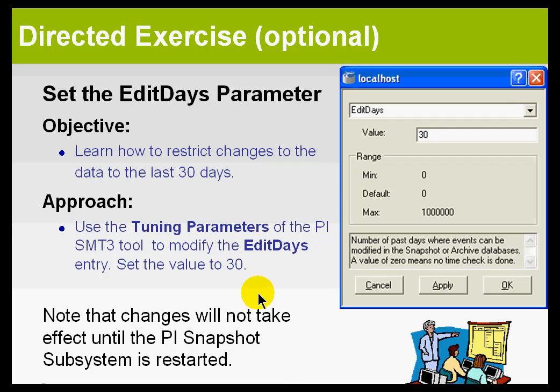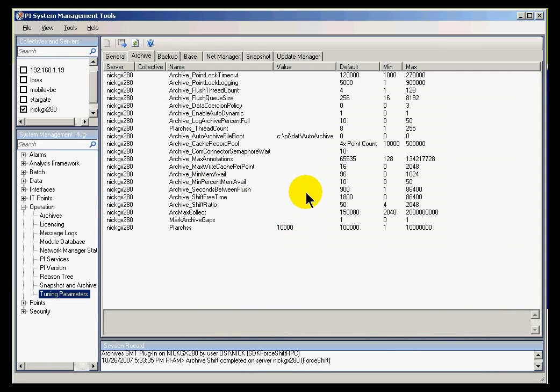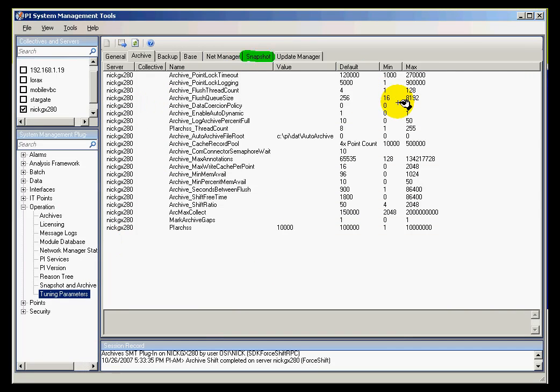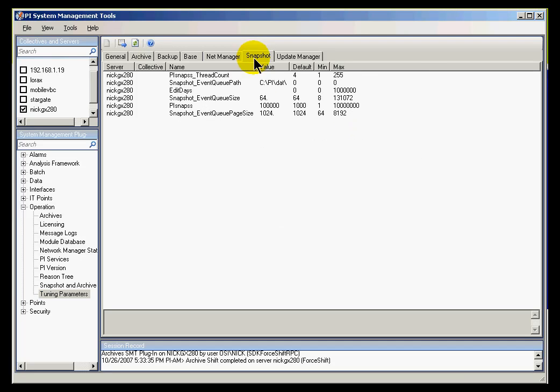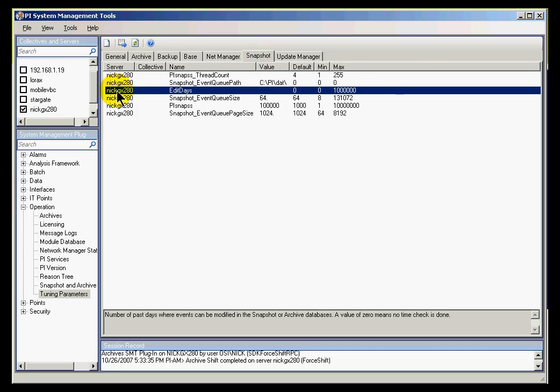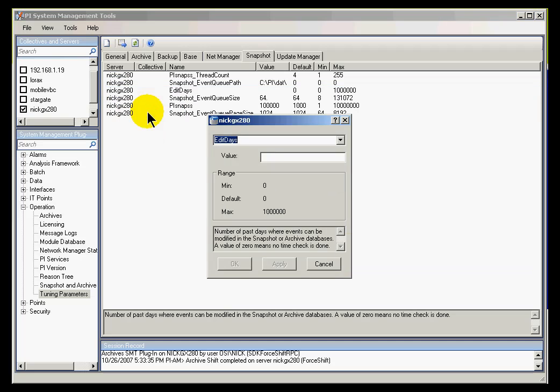I'll show you how to restart the snapshot subsystem. First, let's go into the tuning parameters. I'm going to go into the snapshot tuning parameters. That's where you would find this particular attribute. And you're going to find this right here called Edit Days. I'll choose right-click and then Edit. I'm going to set this to 30.